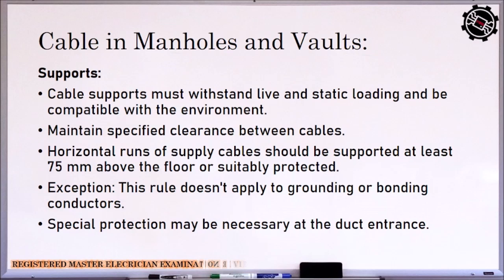So for example, if it is under the street or the sidewalk, it should also withstand the moving load from people or vehicles, and also be compatible with the environment. So if the environment is corrosive, our cable supports must also be resistant to corrosion, or made of non-corrosive materials. So maintain specified clearance between cables.